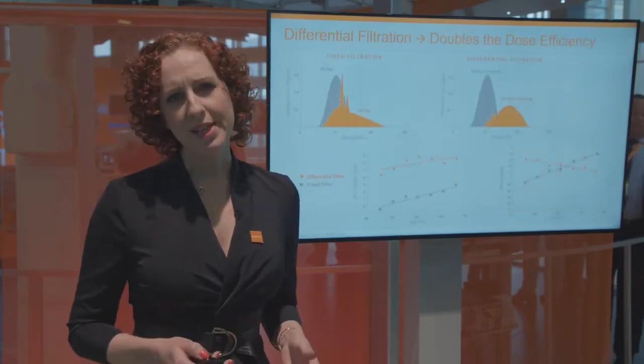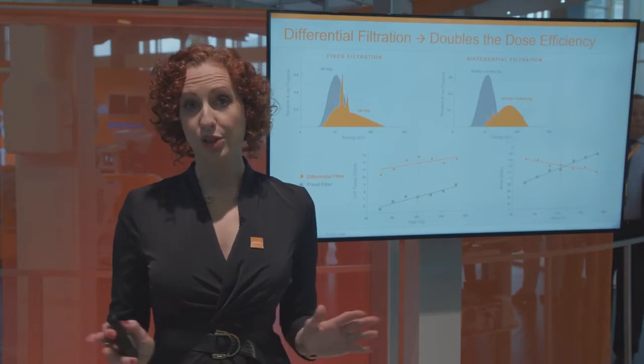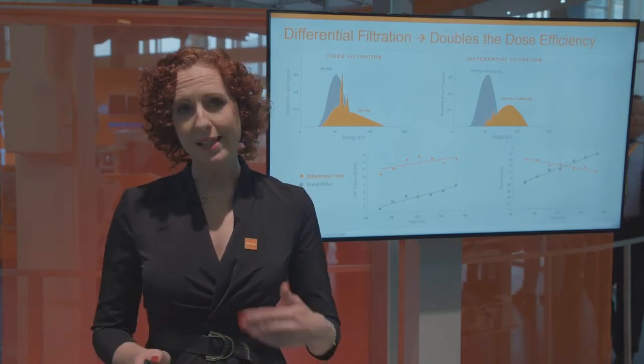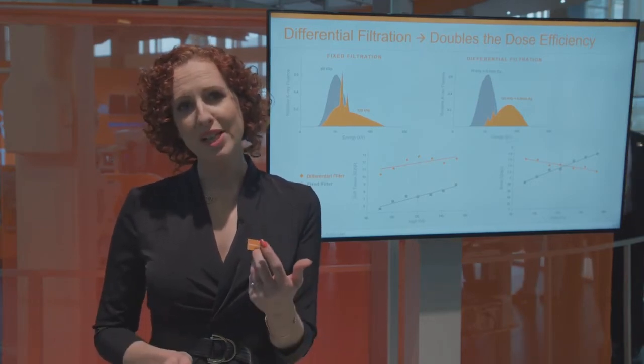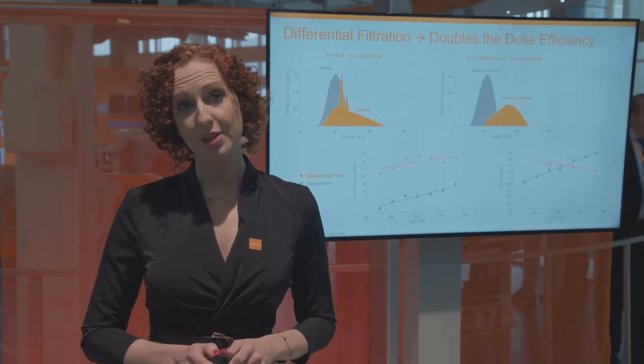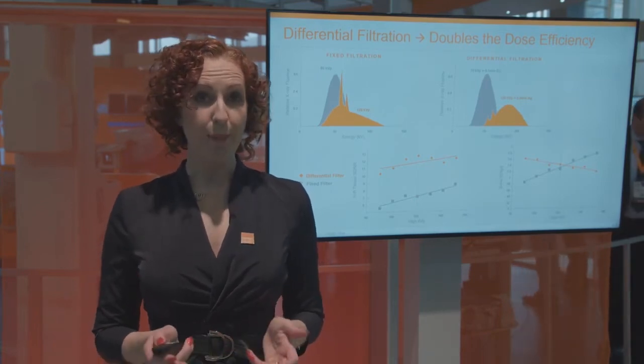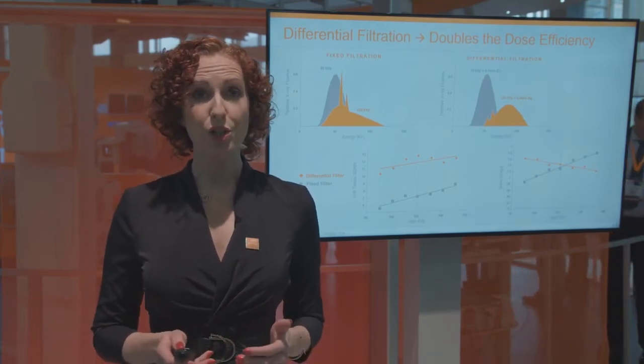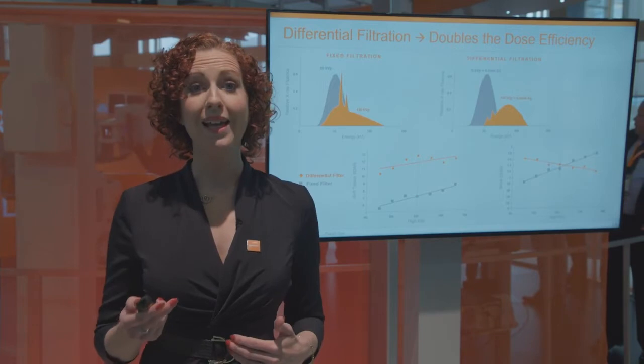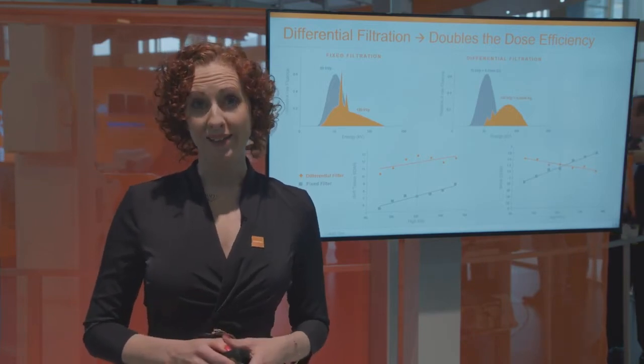Historically, the two limitations of dual energy imaging which have restricted its widespread use are the increase in radiation dose required for two exposures, and image blurring caused by patient motion-induced misregistration between the high and low-energy image pair.